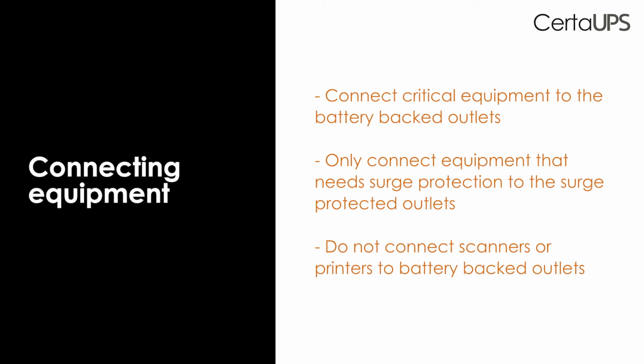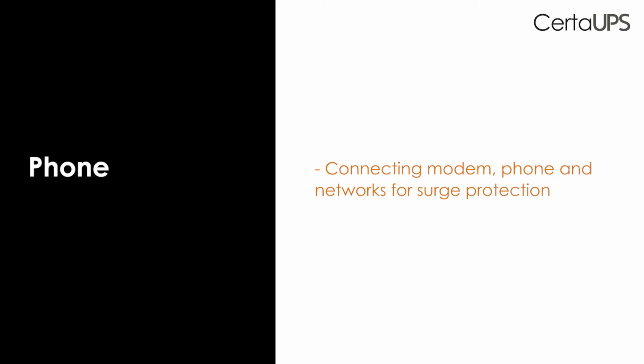Point number 3 is about connecting equipment. Connect critical equipment to the battery backed outlets, which are supported automatically when a mains failure occurs. Connect equipment that only needs surge suppression to the surge protected outlet. You can see there is one on the back of the UPS specifically for surge protection. Please do not connect scanners or printers to the battery backed outlets, because printers and scanners have a high power draw when they initially start up, so we'd have to take that into consideration when sizing a UPS. Number 4 is about connecting modem, phone or network for surge protection.